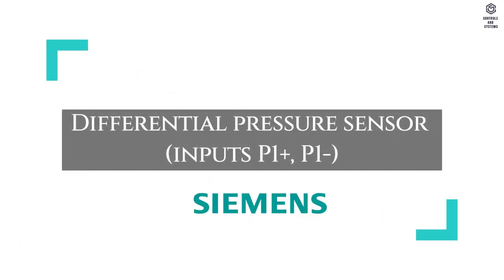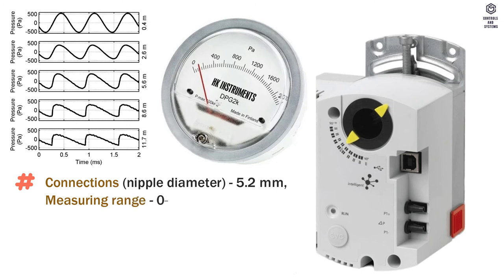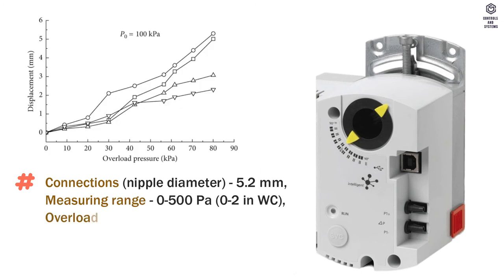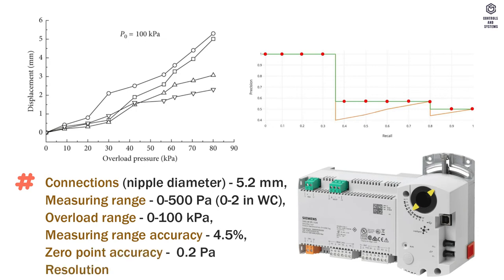Differential pressure sensor connections: nipple diameter is 5.2 mm. Measuring range is 0 to 500 Pascals. Overload range is 0 to 100 kiloPascals. Measuring range accuracy is 4.5%. Zero point accuracy is 0.2 Pascals. Resolution is 12-bit.